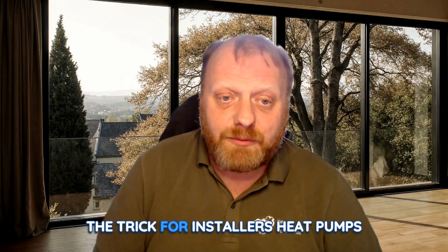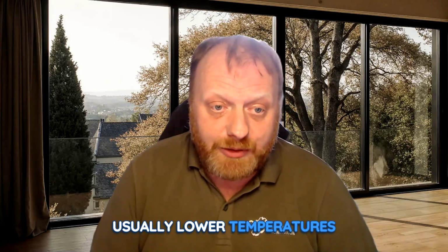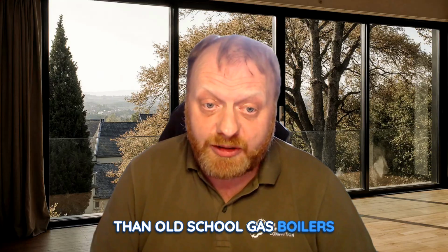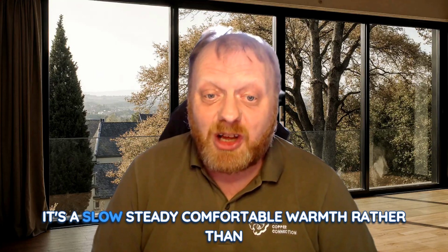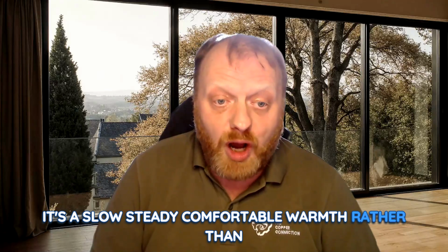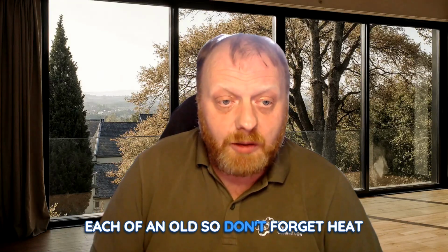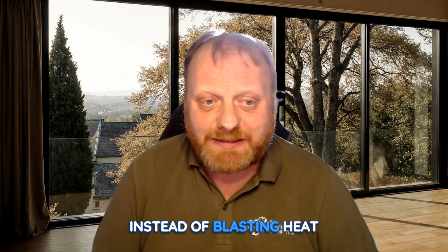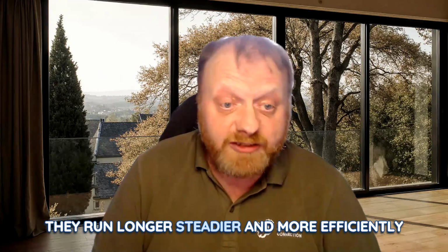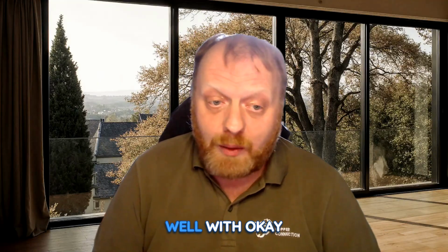Here's the trick for installers. Heat pumps usually run at lower temperatures than old school gas boilers. That's why we often pair them with underfloor heating. It's a slow, steady, comfortable warmth, rather than that scorching heat of an old radiator. So don't forget, heat pumps equals lower temperature systems. Instead of blasting heat, they run longer, steadier and more efficiently. That's why underfloor heating works so well with them.